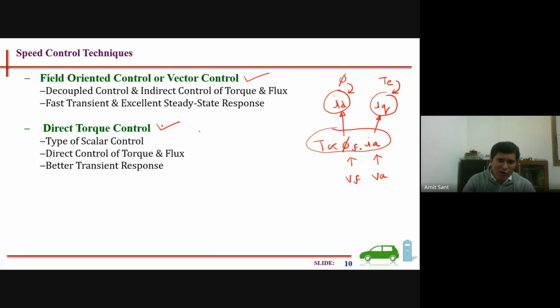Direct torque control says you don't have to control the components of current to control torque and flux. In vector control, flux is proportional to one current, torque to another, and by controlling the current we indirectly control flux and torque. Direct torque control says no, this is not the right way - we will control torque and flux directly.